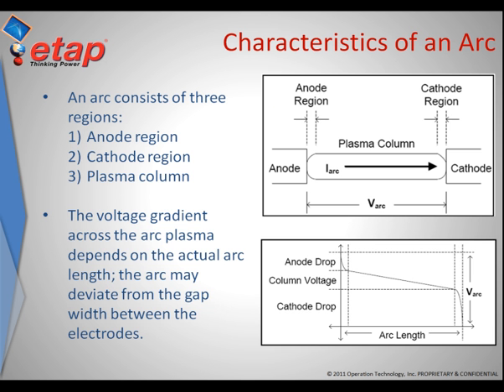The characteristics of an arc in DC ArcFlash are illustrated in the image in the top right hand corner. A positive and a negative conductor, characterized as an anode and a cathode, in which the current flows from the anode region towards the cathode region. This current flows in the form of a plasma column, which will have a voltage drop across it — and that voltage drop is what we call an arc voltage.